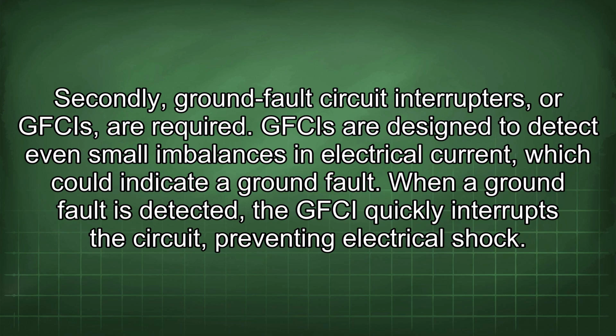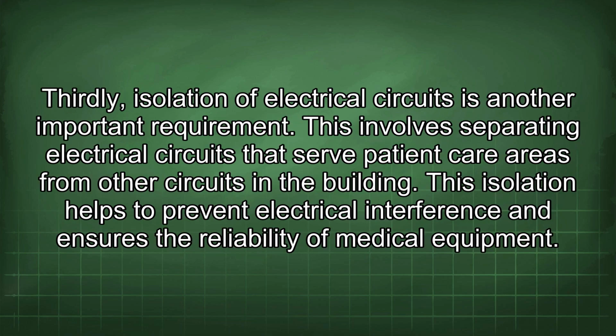Secondly, ground fault circuit interrupters, or GFCIs, are required. GFCIs are designed to detect even small imbalances in electrical current, which could indicate a ground fault. When a ground fault is detected, the GFCI quickly interrupts the circuit, preventing electrical shock. Thirdly, isolation of electrical circuits is another important requirement. This involves separating electrical circuits that serve patient care areas from other circuits in the building. This isolation helps to prevent electrical interference and ensures the reliability of medical equipment.